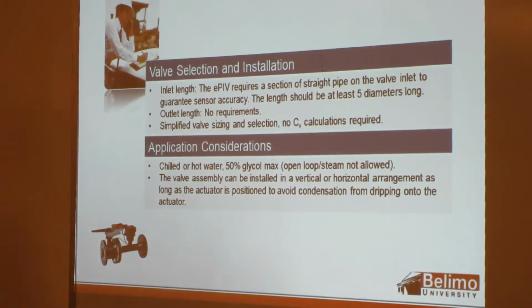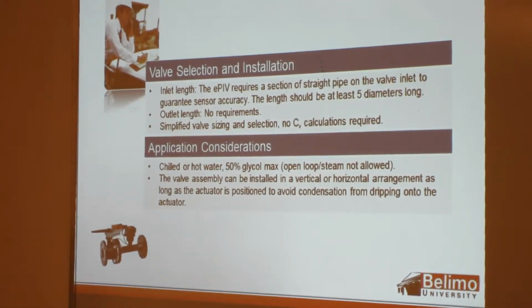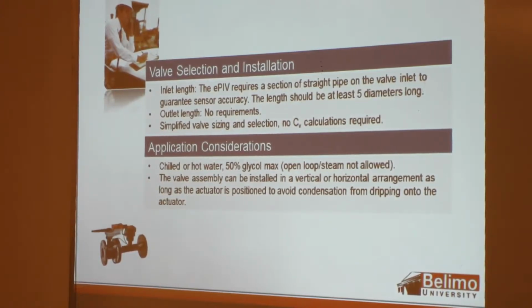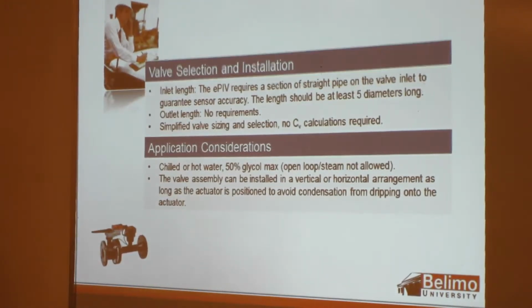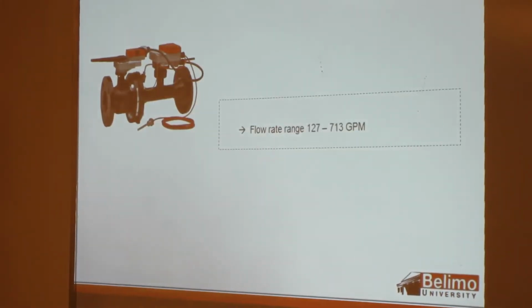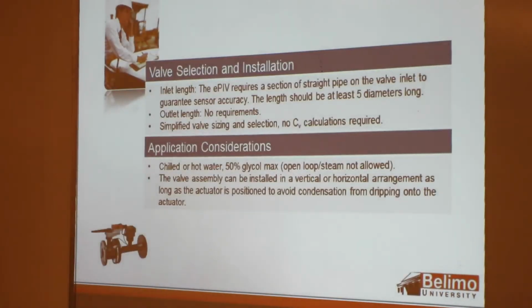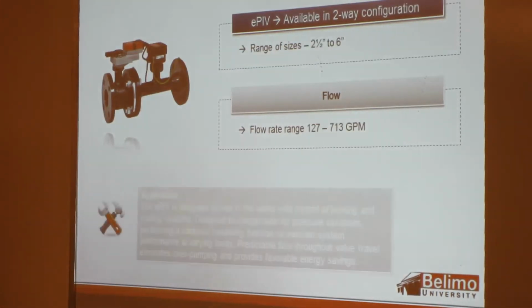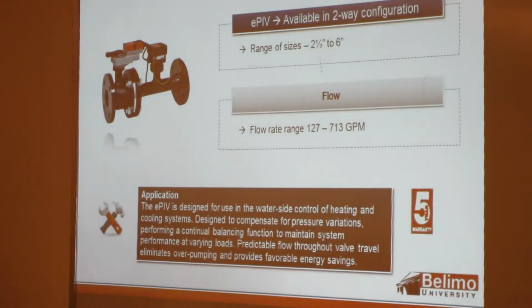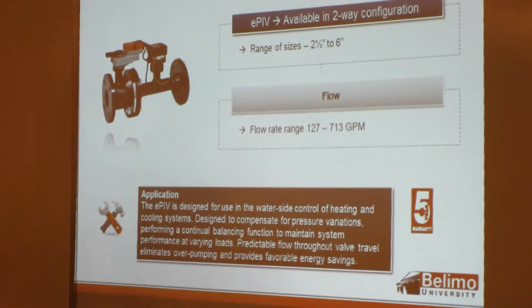Good for hot or chilled water, 50% glycol mix. Again, it can be installed vertically or horizontally, and we don't want an actuator below the valve body. Like I said, one thing I just wanted to point out, a feature of this that a lot of people really like, is that with this magnetic flow sensor, your feedback will give you the flow through the valve.